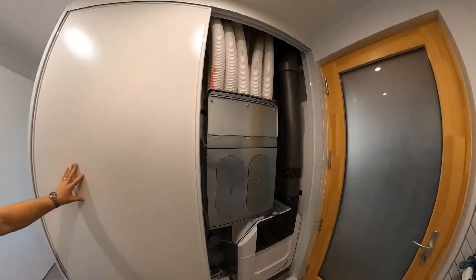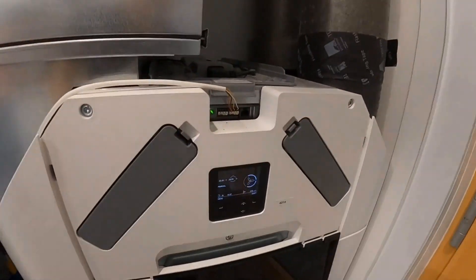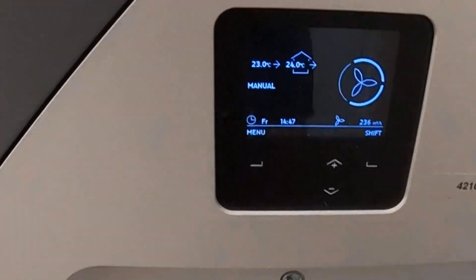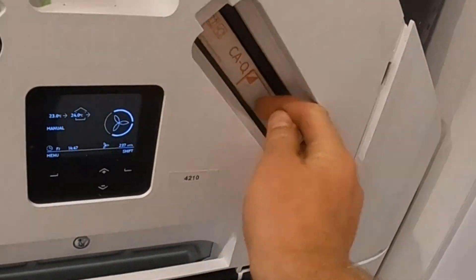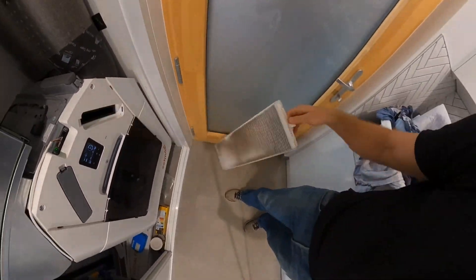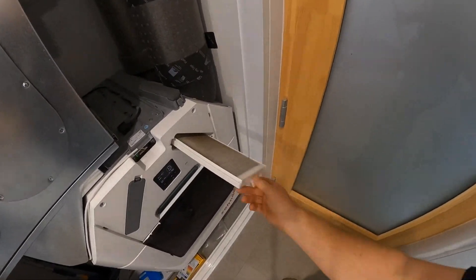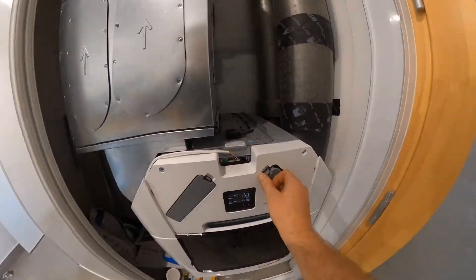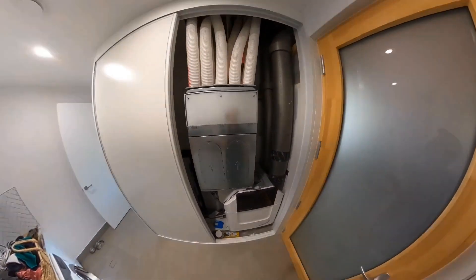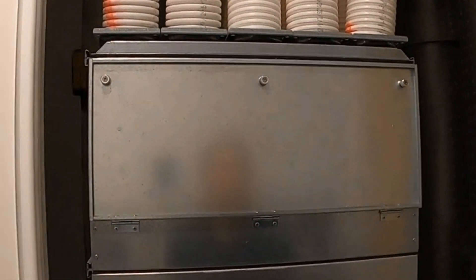This is the laundry, and this is the real heart of a passive house — the mechanical ventilation heat recovery unit that provides a continuous flow of fresh air. You can see the fans working; it's on setting two, monitoring temperature and airflow. These are the filters — this is an F7 high-grade filter that's already quite dirty after just a month of occupation. It's protected us from a lot of dust and particulates by filtering the incoming air through those large insulated air intake and exhaust tubes. These white tubes distribute air from the MVHR out to all the rooms and extract from key points.